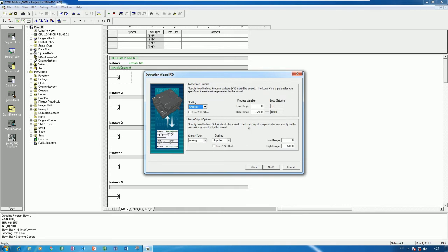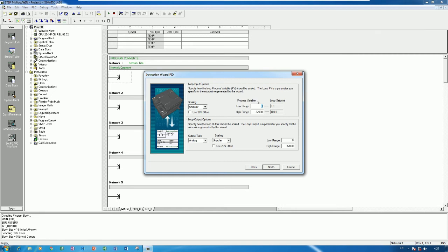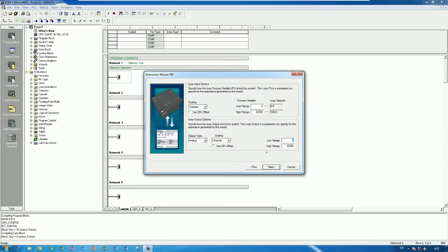And then click Next. And here is the analog PID or digital PID so we can choose, but for this time I will use the analog PID first. And here is the PV process variable 0 to 32,000 for analog input and loop set point 0 to 100%, and here is the high range and low range of analog, 0 to 32,000 also. So let's choose default first.